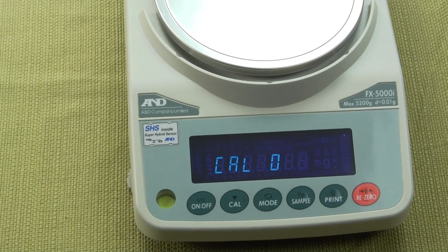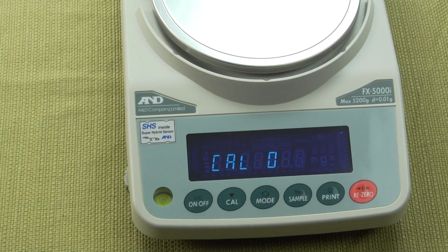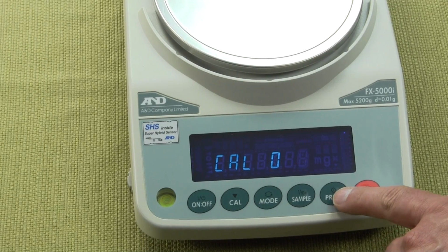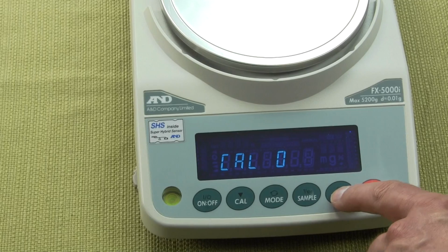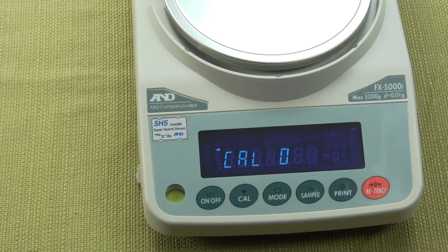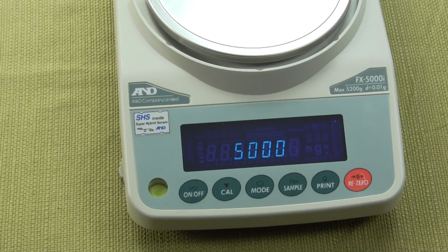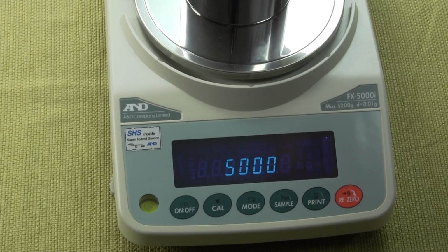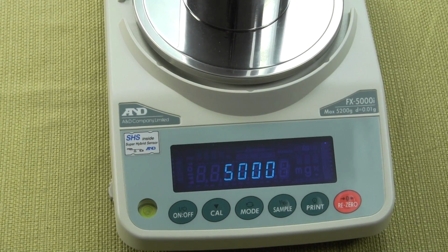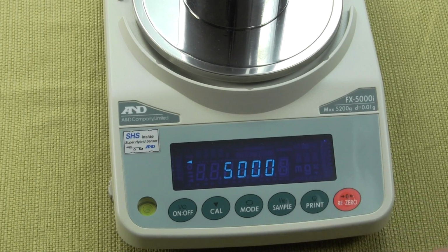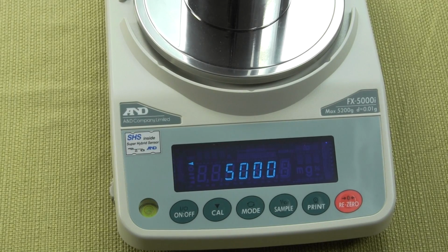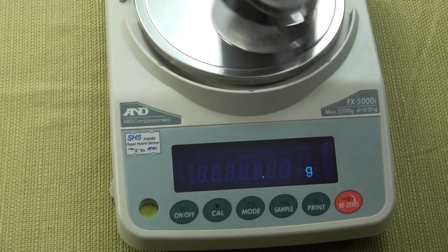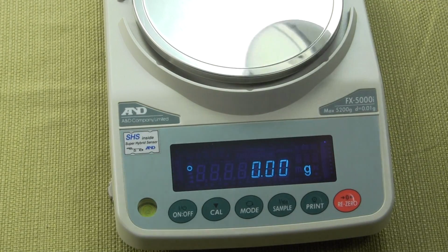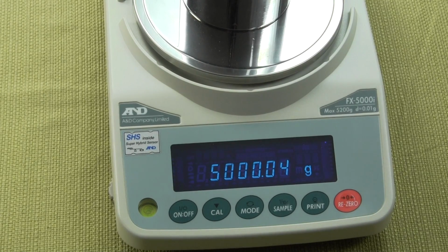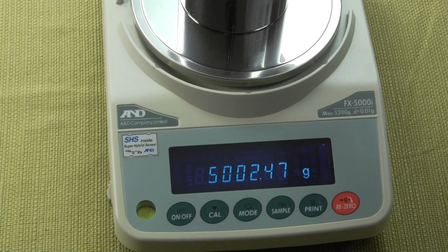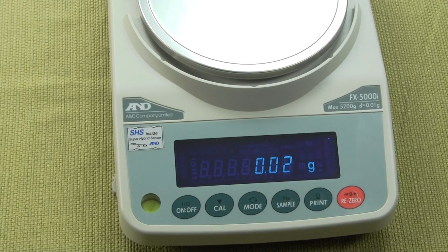So we're back to cal 0, and at cal 0, we're going to be storing the value with nothing on the platform. To do this, we're going to just simply press the print key, and you'll notice up in the upper left-hand corner, the little arrow, it's storing it. So now the balance shows 5,000. We're going to put our 5,000 gram weight on the balance in the center of the platform. And now we're simply going to press the print key again. Again, in the upper left-hand corner, we have that arrow. It's storing the value. Now it says cal end. Remove the weight. Place the weight back on. And there you have it. So we can do the calibration again. I can get it in tighter. But I just wanted to basically show you how to do the calibration.